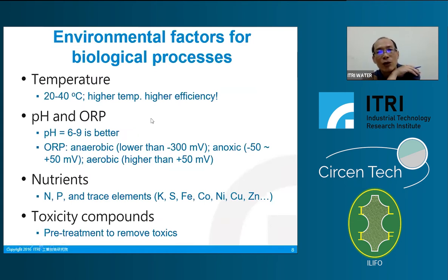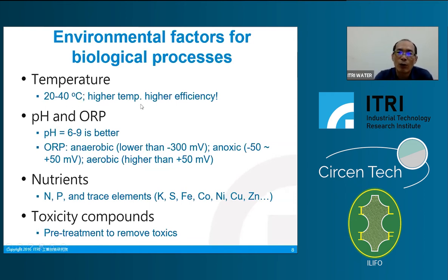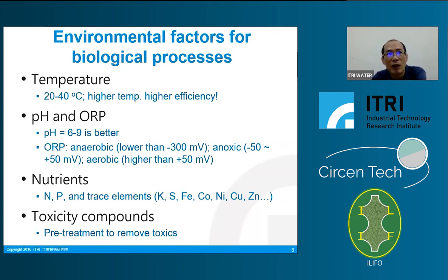Key environmental factors for biological treatment include temperature, ideally 20–40°C, where higher temperatures yield higher efficiency. Below 15°C, efficiency decreases significantly. In places like India where winter temperatures may drop below 10°C or even 5°C, heating may be required to maintain adequate treatment performance.